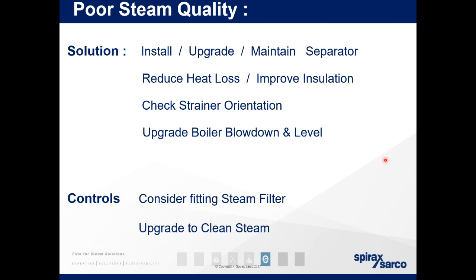It's the same reason we wash our cars and we hoover our seats. We try to keep our cars clean and in good working condition. Same for your steam system. So reducing heat loss, improve insulation. We covered it again. If you've got a crack in your covering on your insulation, which is allowing water in, say from rain or from condensation rather than condensate from the steam line, it's going to absorb heat from your steam system. It's going to cool your pipes. So therefore it's going to introduce wet steam into your process, but it's also going to cost you more to run your boiler.